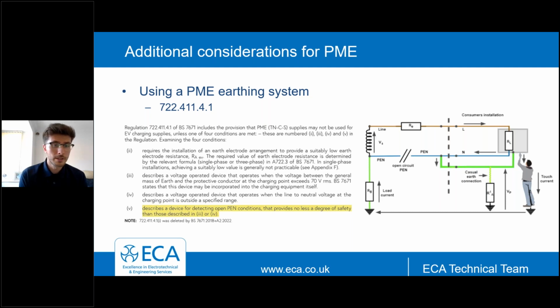Indent 3 is the first of the voltage operated devices. This monitors the voltage between the general mass of earth and the protective conductor at the charging point, and should disconnect if the voltage difference exceeds 70 volts RMS. Again, this is not one of the more common measures to use, and it may, subject to manufacturer's instructions, also require an additional earth electrode to be installed.